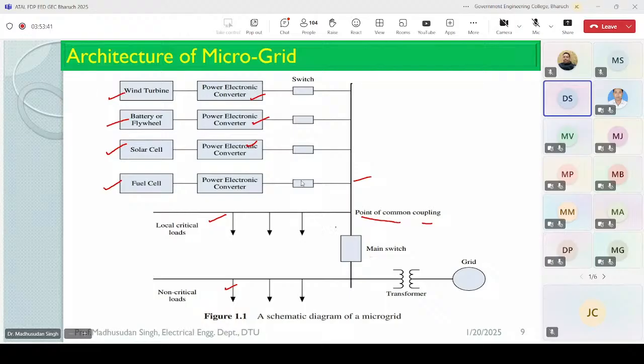Especially when you operate in islanded mode - when you open this switch, this isolator - you ensure that supply to the critical loads is managed by these local resources, and these sources of energy are maintained in such a way that the voltage and frequency of this network remains within prescribed limits. So that is the priority of this grid: even if your normal grid is not available, you can meet the requirement of high demanding load. Such a critical load could be a hospital load, a military base, or any other similarly important load.